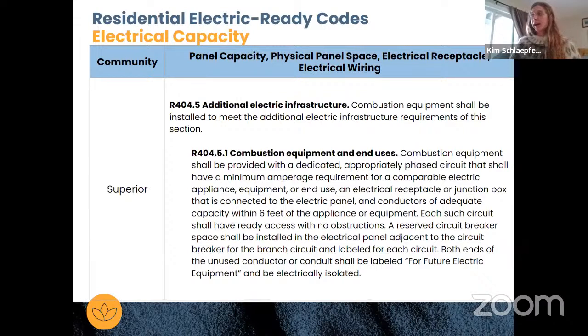Okay, so I'm hearing that we kind of like the approach of Superior, but that we have an opportunity to add some specifics. The specifics I've heard are a 2-pole circuit breaker minimum, or space for that, physical space for the air handler unit as well as the appliance, and a condensate drain for the condenser, which was brought up last meeting.